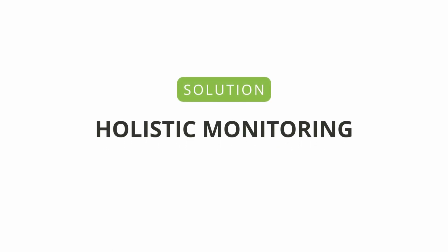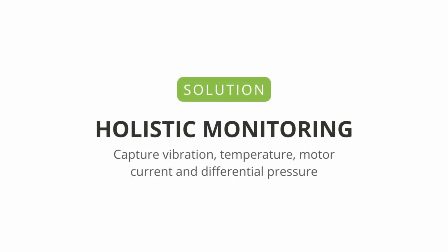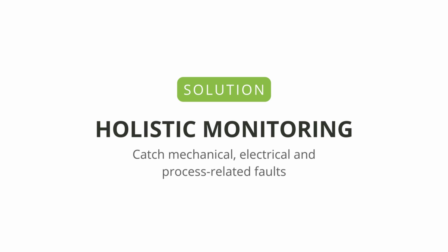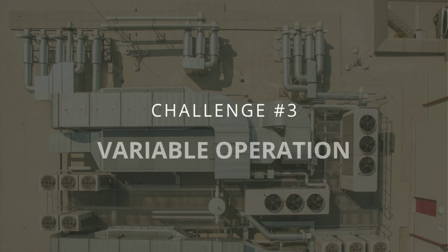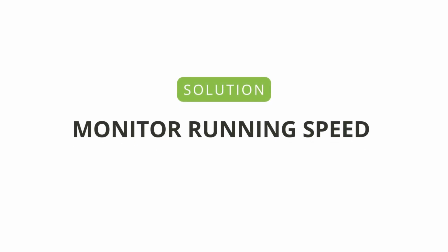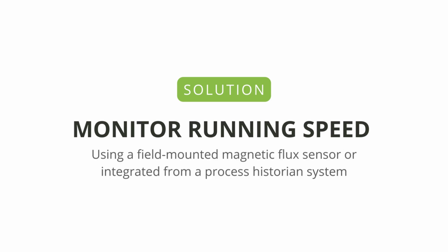The solution is to take a holistic monitoring approach that captures vibration, temperature, motor current, and differential pressure to catch mechanical, electrical, and process-related faults, including clogged filters. Challenge 3. Variable operation. Most AHUs operate at variable speeds and under variable loads to meet demand. Without knowing the operating context at any given time, it's difficult to baseline what normal looks like in terms of vibration or temperature data. The solution is to include running speed in your monitoring strategy. This can be captured either by a field-mounted magnetic flux sensor or integrated from a process historian system, giving you the context needed for interpreting different trends.